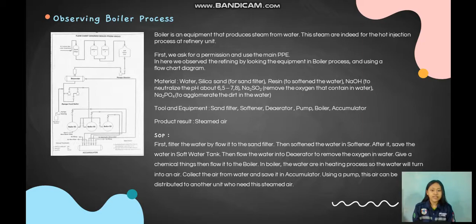SOP. First, filter the water by flowing it to the sand filter. Then soften the water in the softener. After that, save the water in the soft water tank. Then flow the water into the deaerator to remove the oxygen in the water using the chemical Na2SO3. Then add the chemicals, then flow it to the boiler. In the boiler, the water is heated, so the water will turn into steam. Collect the steam and save it in the accumulator. Using a pump, this steam can be distributed to other units that need it.